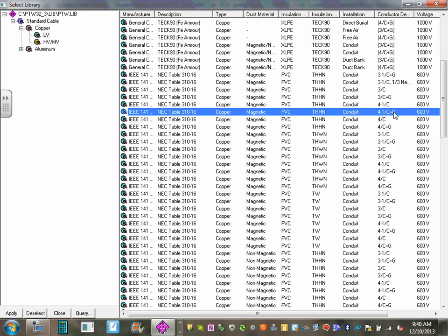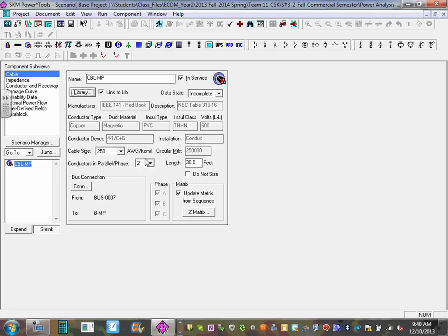There are four conductors, four single conductor plus ground. That's what we're going to pull. Double click on it. Okay, then exit. If it doesn't take you there, just see where that X exit is. Now, can you guys see that it changes my insulation? The size is still the same, though. The length is 30 feet. I'm using 30 feet between all of them, so that's not a bad assumption.